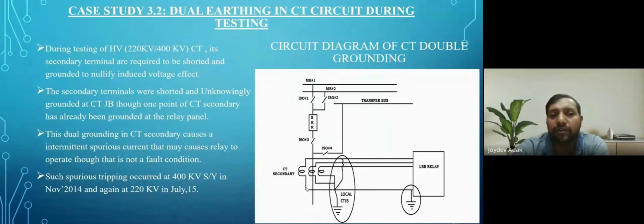During the testing of the relay, another grounding was done. During the testing, induced voltage was created, and due to this induced voltage, current flowed through the relay and continued through the grounding path, and due to that the LBB relay operated, with the other condition also satisfied. For the LBB relay there are two conditions. One is the current, and the lockout relay is also there. The lockout relay was not reset. The lockout was in the operated condition for this breaker.